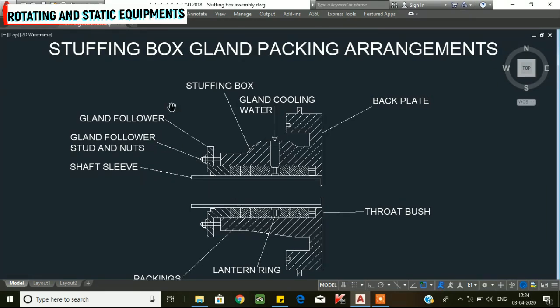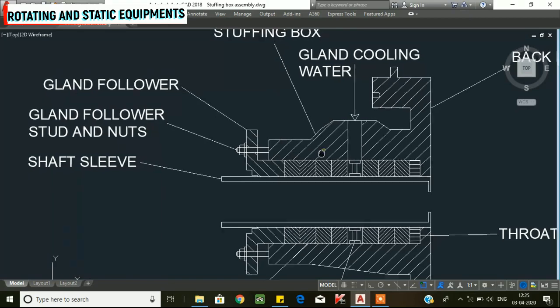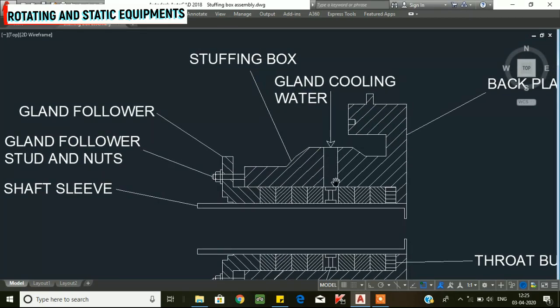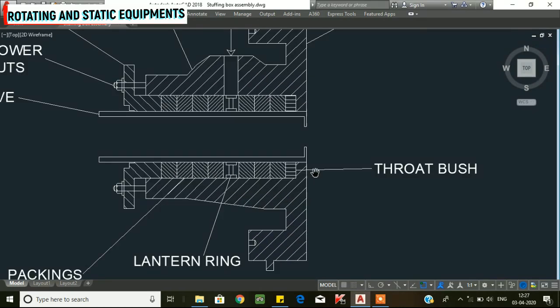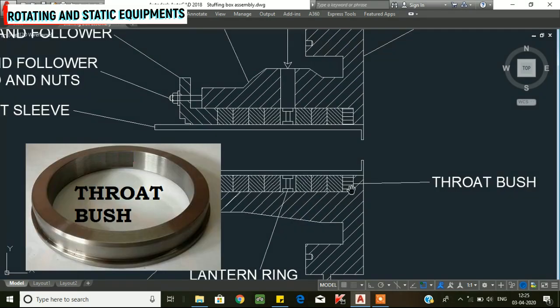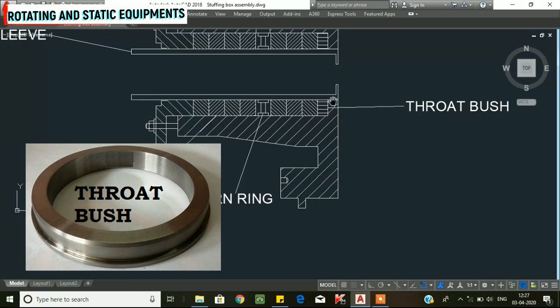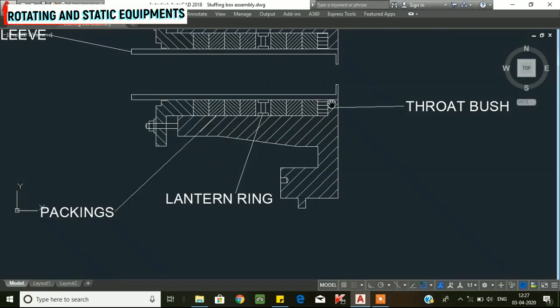Now we will see the stuffing box and its components: the shaft sleeve, gland follower, back plate, and throat bush. The throat bush is important because in the sleeve and stuffing box area, the gap and clearance will reduce, which is why we use the throat bush.